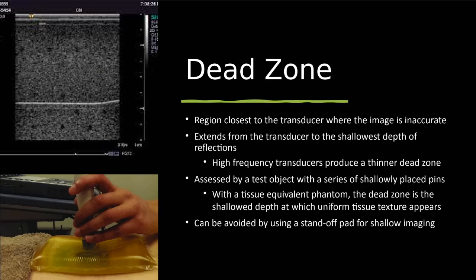Our dead zone, so we kind of talked a little bit about this, not too much, but this is the region closest to the transducer where the image is going to be inaccurate. So if you look at that top image, that represents the top of our transducer, right? The anterior most portion of anatomy, and we can't really evaluate that layer. So I think I showed a few of you when we were learning about standoff pads and all of those things. If you have a really superficial lump, if you put jelly in the transducer right on that lump and you put your average amount of pressure, you're not going to see it because it falls right in that dead zone. So you need some sort of standoff pad to get that focus out of the dead zone. And that is for this reason.